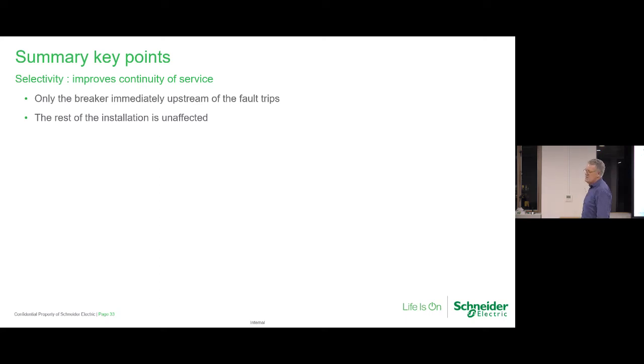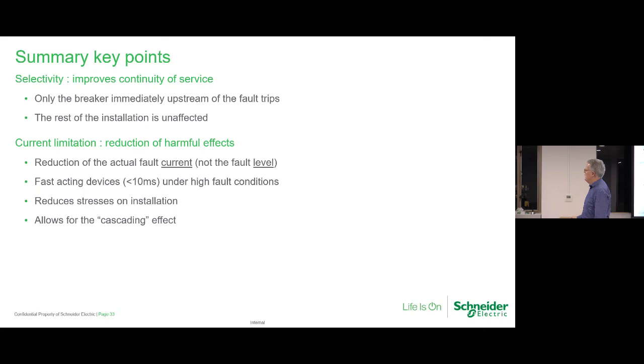Selectivity improves continuity of service. Pretty standard, isn't it? Only the breaker immediately upstream, the rest of the installation unaffected. Key: current limitation, reduction of harmful effects. Look at all the benefits. Fast acting, reduces stress on installation, allows cascading effect, which we know is the money area.